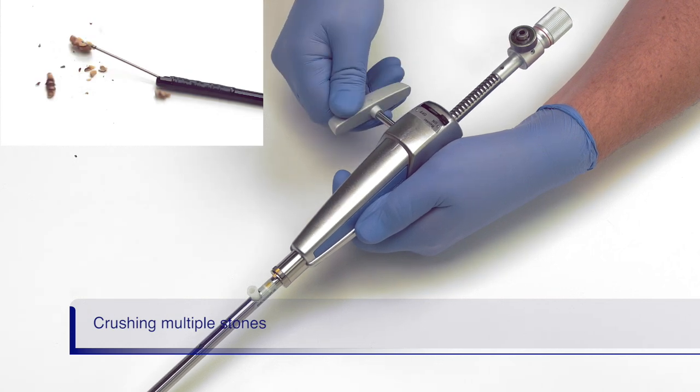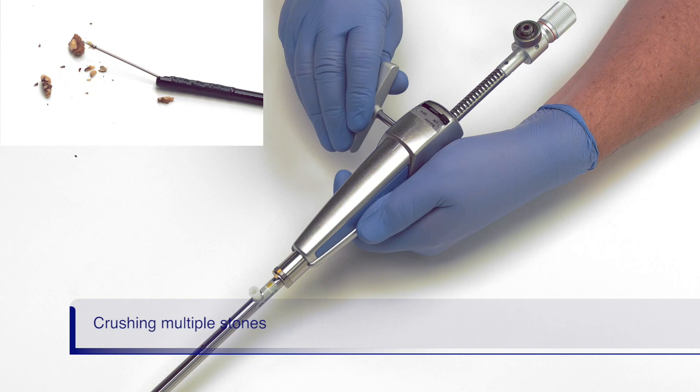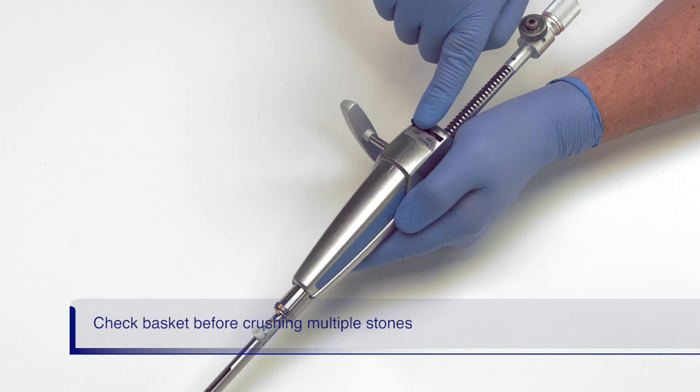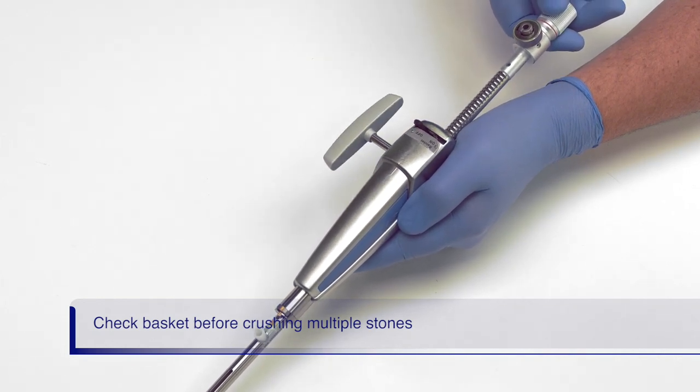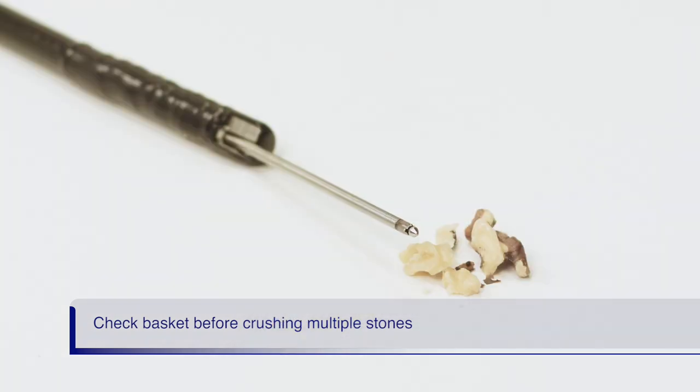LithoCrush V can be used to crush multiple stones. However, you will need to crush each stone one at a time. Turn the ratchet off and check that the basket can reopen smoothly. Apply gentle pressure to the back of the handle to reopen the basket. Smoothly open and close the basket before crushing additional stones. If the basket does not smoothly open and close, then remove it from the patient and use a new basket to ensure no trauma is done to the duct.